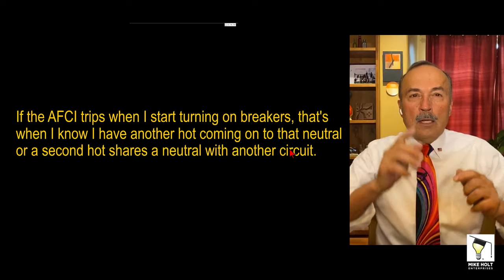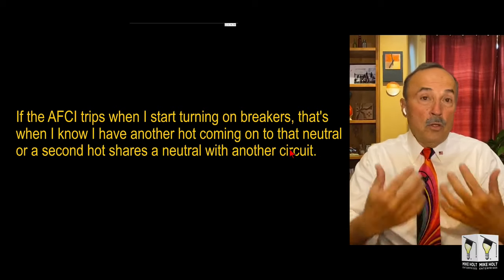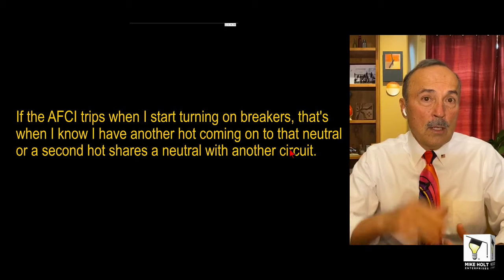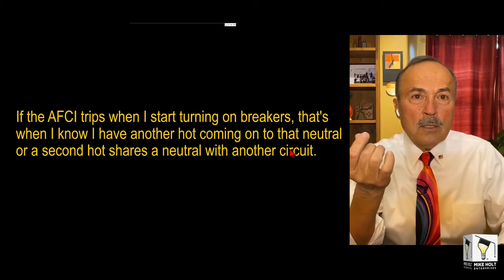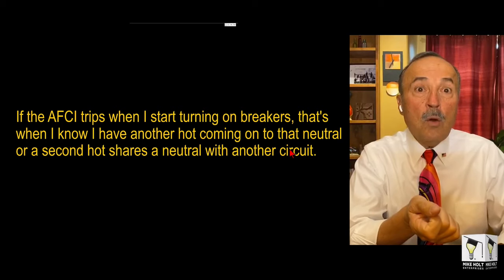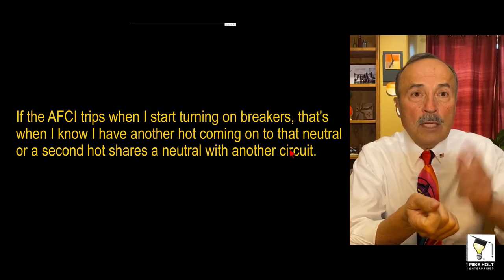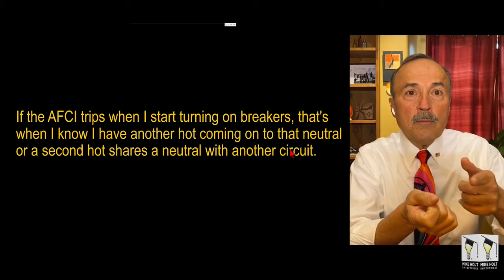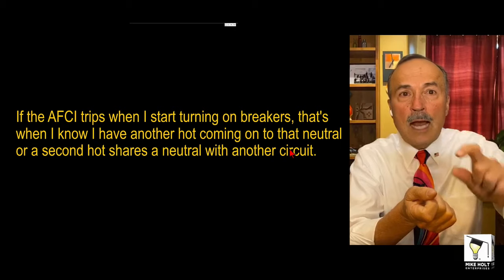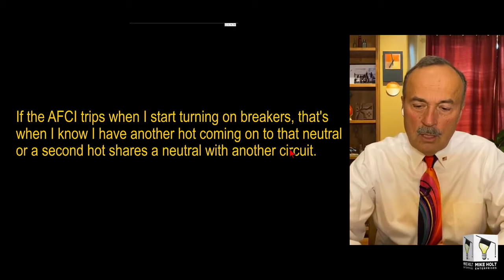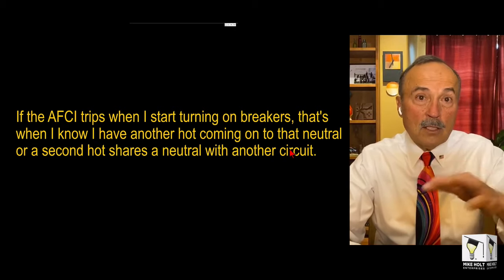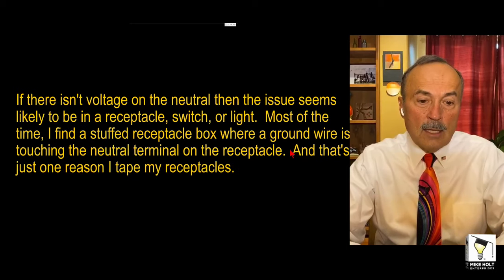So, like, this one's tripping. What I would prefer is to leave the breaker up. Don't take the wire off the breaker. Put an ammeter on that neutral, then just start turning off breakers till you find out which breakers are common to that neutral. You guys know how to troubleshoot it, so I don't get into that detail. It's a divide and conquer kind of thing.